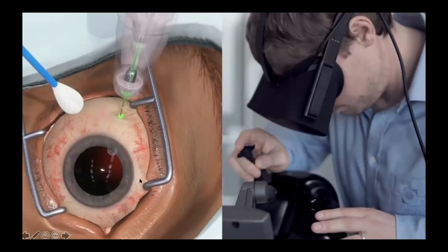Here you can see the refill procedure being performed similar to an intravitreal injection with a specialized refill needle that allows for simultaneous injection of fresh drug, fresh ranibizumab, as there is reflux of the old drug from the port coming back out into the needle. So there's a refill, a replacement of the medication.